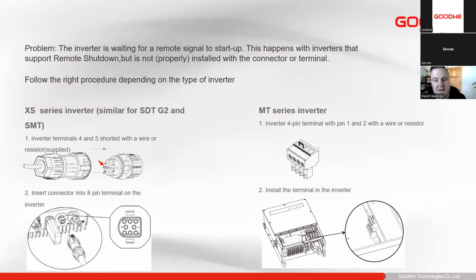those plugs. We get it very often that it is ignored because it's not something that's used, and then once we start to commission the system, it might be a few weeks or months later and we've thrown it in the trash. Now the inverter cannot work without it, and then you need to contact us to try and get a new one. So please always make sure any of these proprietary plugs that are in the accessories, always just install them on the inverters. That way you'll know the remote disconnect is inserted and it shouldn't be a problem.